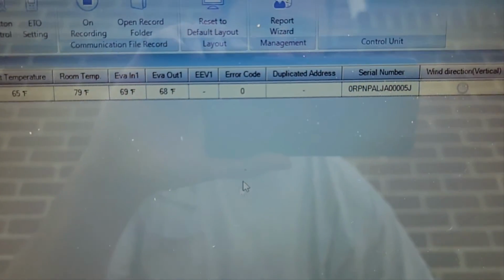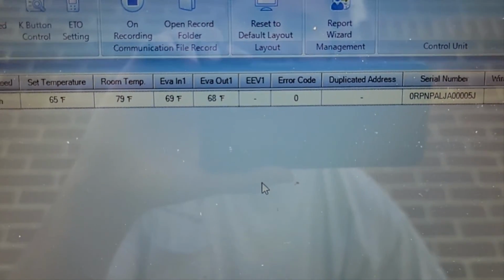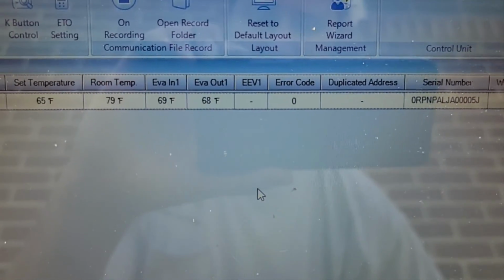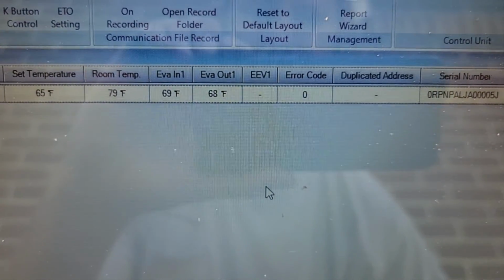Indoor unit data. Oh, looky there, evaporator inlet is no longer 150, it's 69. Evaporator outlet is 68. These are going to read about the same, especially when the unit's off, so keep that in mind.